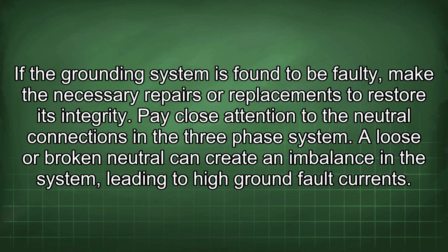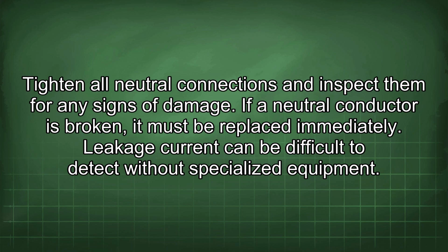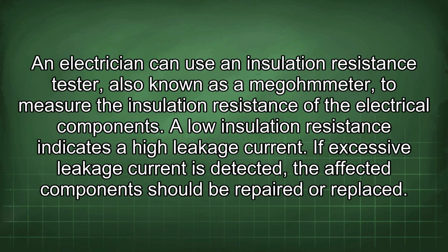Pay close attention to the neutral connections in the 3-phase system. A loose or broken neutral can create an imbalance in the system, leading to high ground fault currents. Tighten all neutral connections and inspect them for any signs of damage. If a neutral conductor is broken, it must be replaced immediately. Leakage current can be difficult to detect without specialized equipment. An electrician can use an insulation resistance tester, also known as a megohmmeter, to measure the insulation resistance of the electrical components. A low insulation resistance indicates a high leakage current. If excessive leakage current is detected, the affected component should be repaired or replaced.